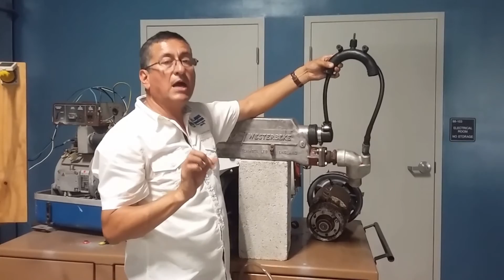You need one anti-siphon located here if the generator is located below the water line. You need another one. The raw water pump should be located below the water line. After that, after the raw water pump, the raw water enters here into the heat exchanger, passes through the heat exchanger, and goes out.